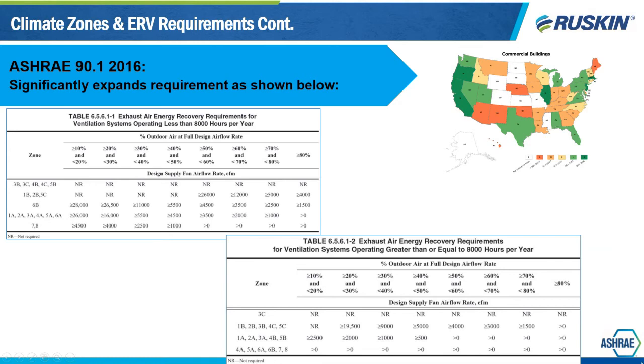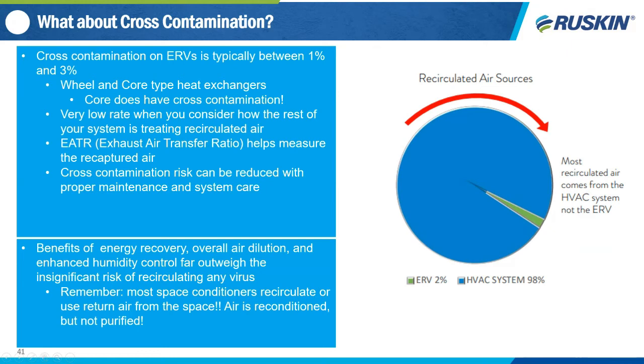Next slide. And what about cross-contamination? So this is a great question and a great discussion that we always have. On a wheel, you are typically going to see about 3% cross-contamination. On a core, it's typically going to be between 1 and 3% cross-contamination. There is a very common misconception out there that there is no cross-contamination with a core. Unless you are dealing with a non-permeable core, which most of the energy recovery companies out there designed for commercial buildings are not using, you are going to have cross-contamination. So a wheel and a core, both are going to have cross-contamination, but you're looking at less than 3%.